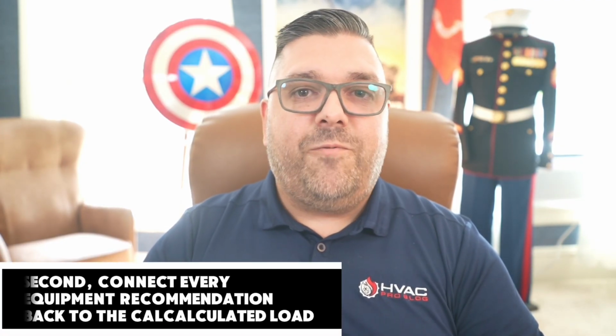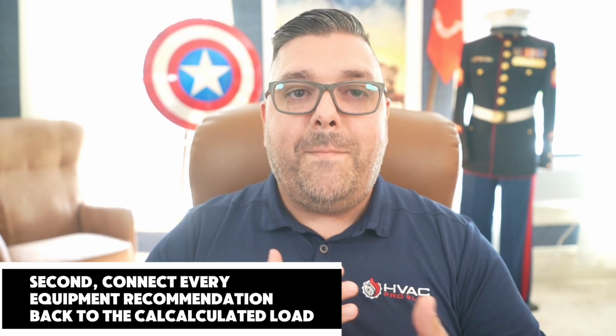Second, I connect every equipment recommendation back to the calculated load. Your home requires 28,400 BTUs of cooling—here's why this particular system at 30,000 BTUs gives us the perfect match with room for efficiency optimization.